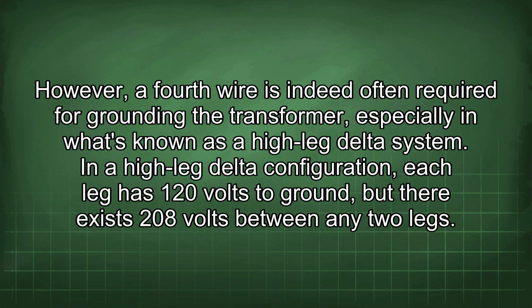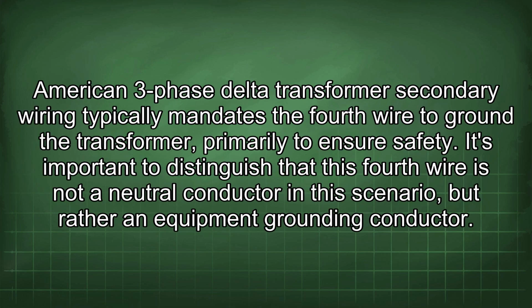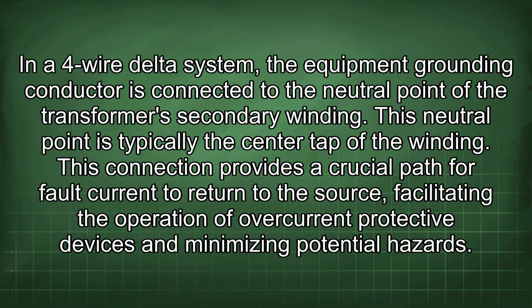American 3-phase delta transformer secondary wiring typically mandates the 4th wire to ground the transformer, primarily to ensure safety. It's important to distinguish that this 4th wire is not a neutral conductor in this scenario, but rather an equipment grounding conductor. In a 4-wire delta system, the equipment grounding conductor is connected to the neutral point of the transformer's secondary winding. This neutral point is typically the center tap of the winding.